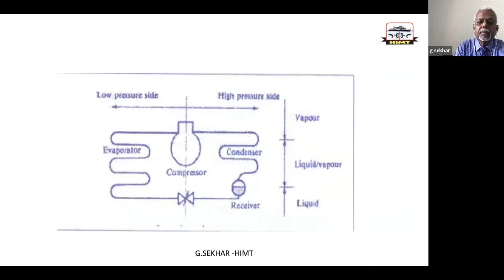Now see here, the compressor is there, and the pressure temperature chart I was talking about. You see the compressor suction pressure is 1.1 bar and discharge pressure is 10.9. From where did he take this 10.9? From the chart. But what exactly is the actual temperature? 93.3 degrees centigrade. You see the compressor discharge temperature here. Compressor discharge pressure is 10.9, but the temperature is 93.3 degrees centigrade. But how much is the superheat here? At 10.9 bar, if the temperature goes below 46.1, then what will happen? It will turn into, come on, complete my sentence.